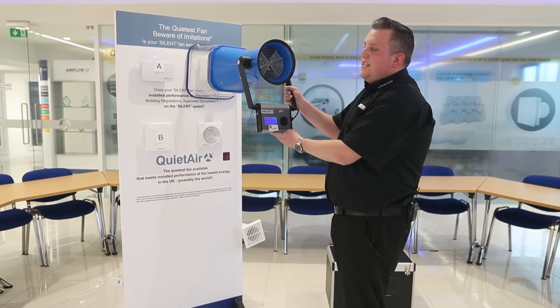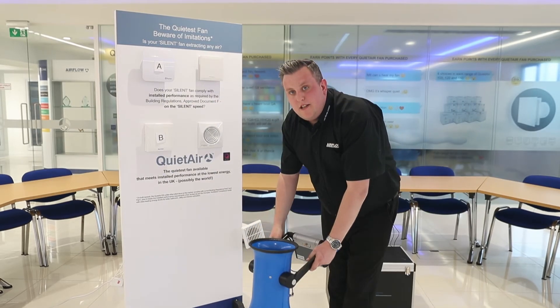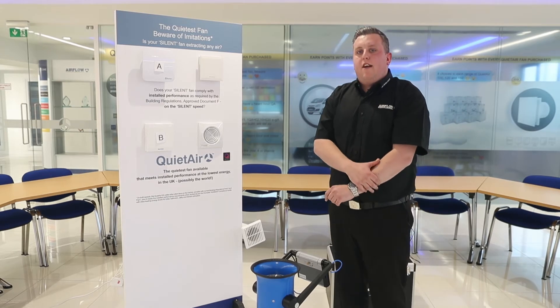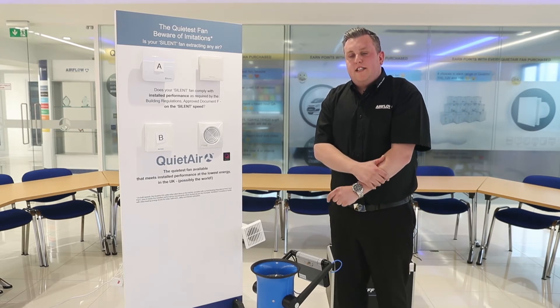As you can see, we've hit 17 litres per second with 1.5 metres of ducting, 2 90-degree bends, and a 90% free air grill on the outside. The QuietAir delivers the quietest installed performance.